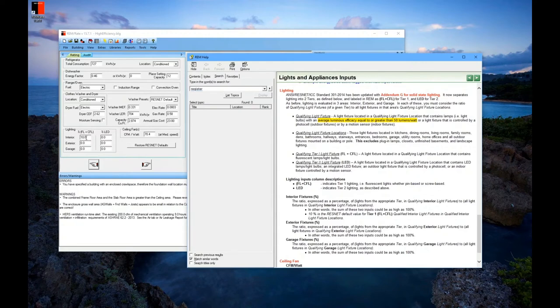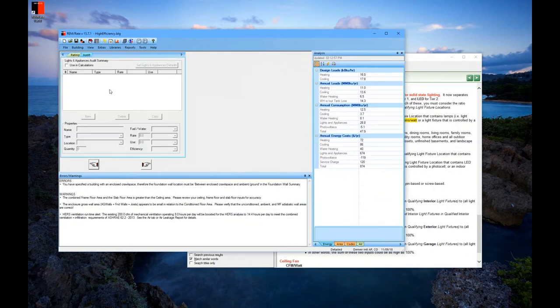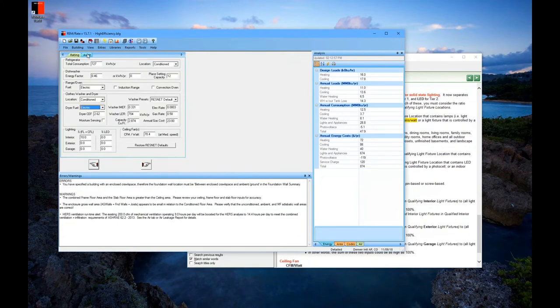For mechanical ventilation, select the ventilation type — balanced systems allow entry of heat recovery efficiency; exhaust-only systems do not. Enter hours and watts accordingly. Natural ventilation for cooling via operable windows is also an option. For appliances, hitting 'Restore RESNET Defaults' populates default values for refrigerators and all appliances per ANSI/RESNET 301. You will need to specify range/oven fuel, dryer location, dryer fuel, and lighting. For lighting, identify what percentage of fixtures are fluorescent, CFL, or LED to take credit for efficient lighting.